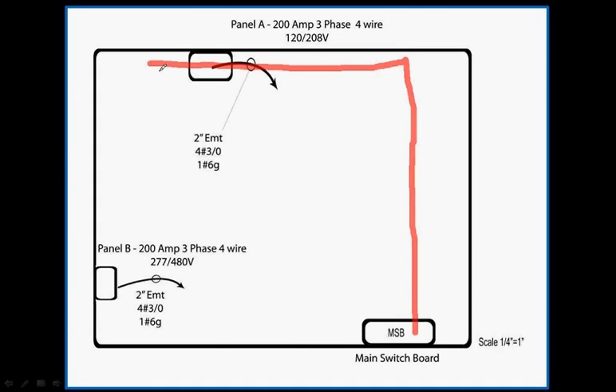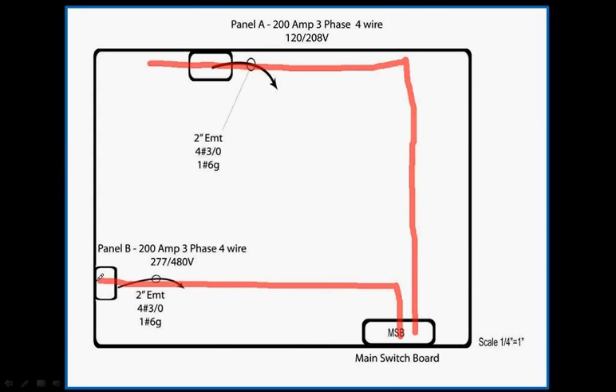I'll finish showing you how to roll off conduits, then I'll show you the material takeoff sheet and what it looks like. I measure or roll off the conduit run feeding panel B the same way I did for panel A. I'm going to say that the scalex reads 140 feet for the conduit feeding to panel B. I write this information down on the takeoff sheet. Now I go to the takeoff sheet to show you how it would look with all the information written down for multiple conduit runs.